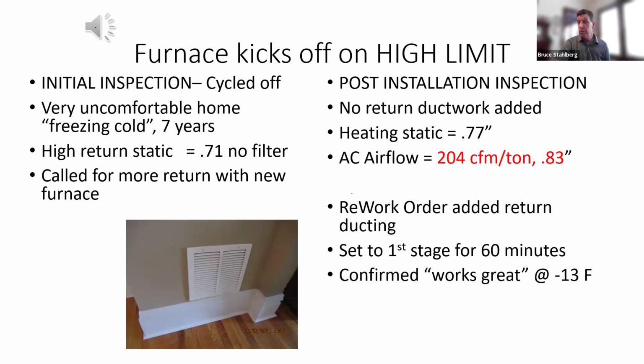The airflow was low on the air conditioner, so I wrote up a rework. We added a return duct, and we set the first stage to run for a long period of time. What that means is, in this case, it's a Goodman furnace. You can set it up for 60 minutes, and that kind of buys us a little bit of time. So it may not ever go to second stage, but if it does, it's after 1 hour, and it's going to be a much shorter run time.